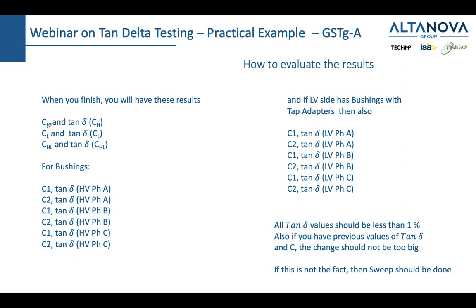CH, capacitance between the high voltage winding and the ground, and the tan delta of that insulation. CL, so capacitance of the low voltage winding and the ground, and CHL, capacitance between the high voltage and low voltage winding. So this is what you would get. This is the body. And then you would get C1 and C2 for phase A on the high voltage side, C1 and C2 for phase B, and the one for phase C. And if you measure the low voltage side, you would get the same set of information.